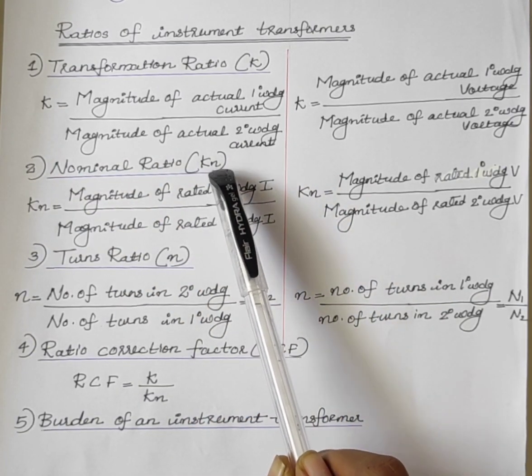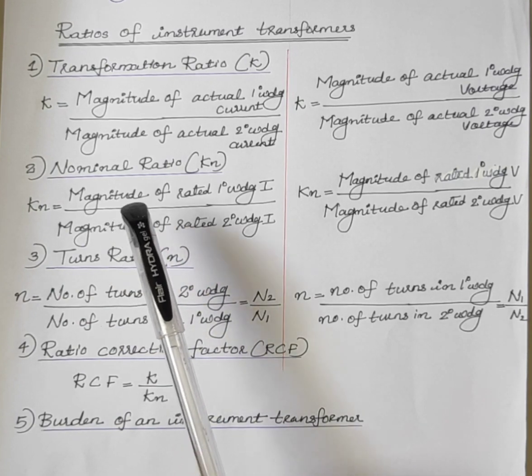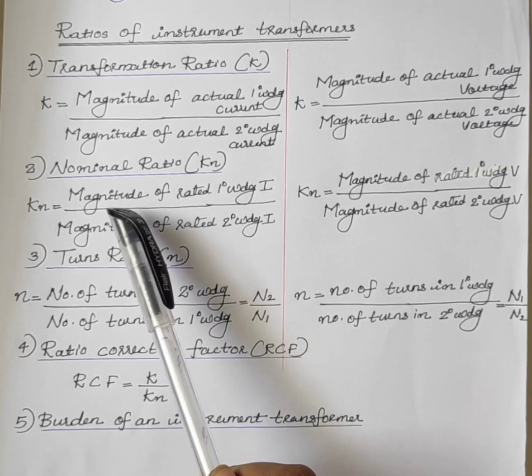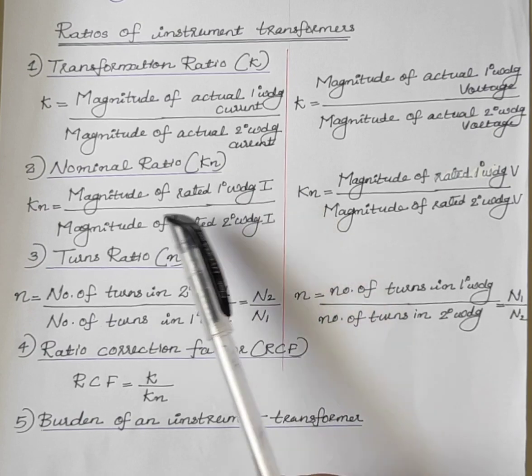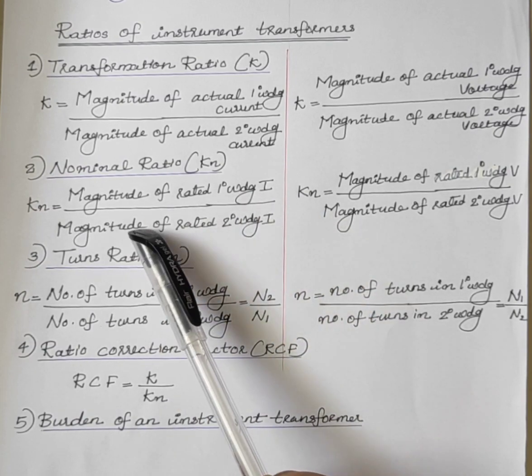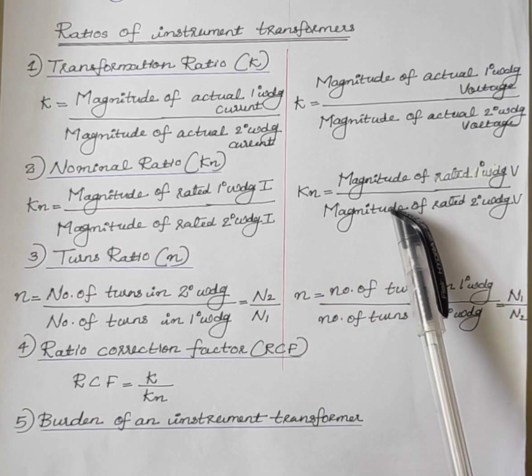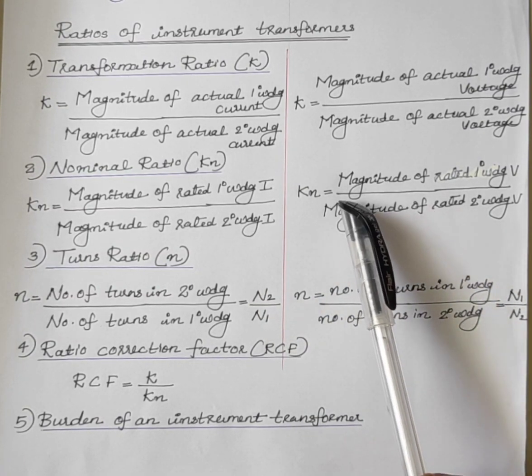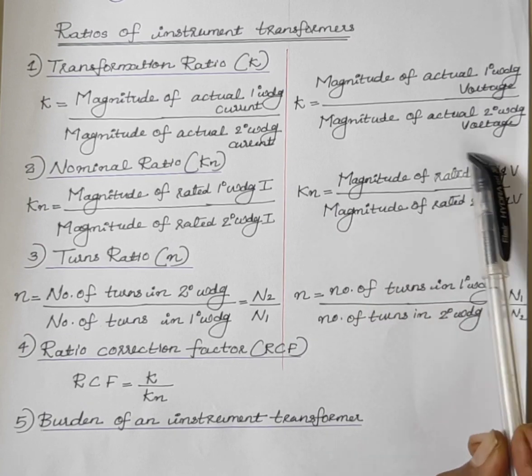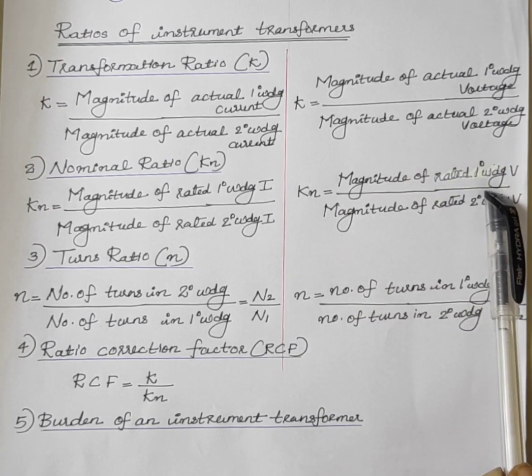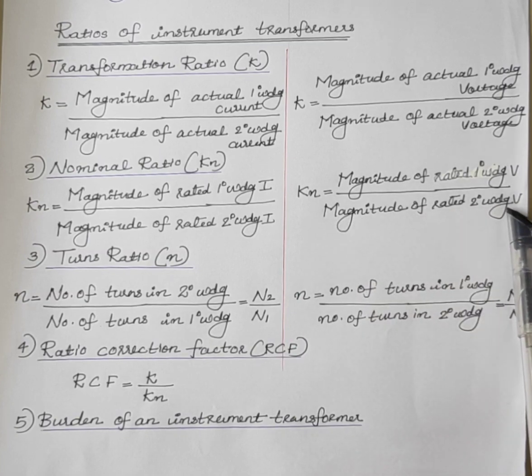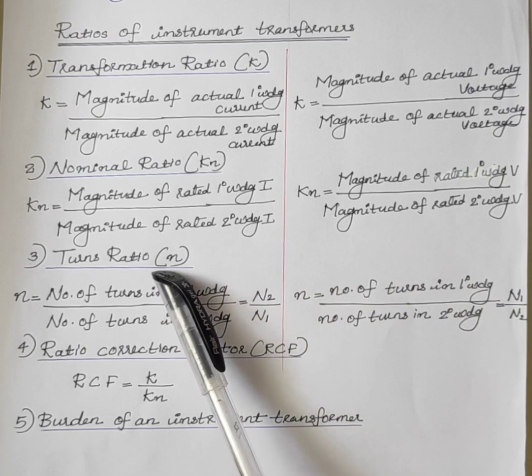Next is the nominal ratio, represented by KN. The nominal ratio of a current transformer is the ratio of the magnitude of rated primary winding current to the magnitude of rated secondary winding current. In the case of a potential transformer, KN is the ratio of the magnitude of rated primary winding voltage to the magnitude of rated secondary winding voltage.